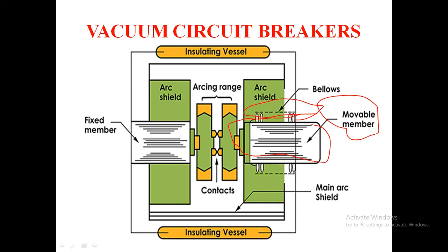The contacts are made with large disc-shaped faces. They have symmetrical grooves so that the segments of the two contacts do not line up along the same line. This facilitates the arc, so that instead of remaining stable at one point, it will be in a diffused state. So it will not remain in the same state. The capability is to retain high vacuum.